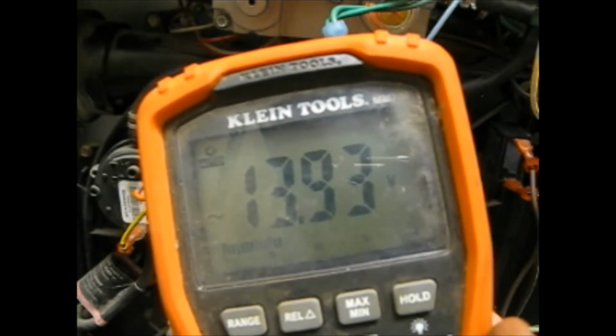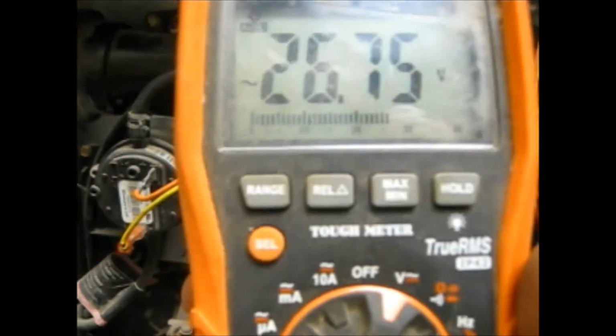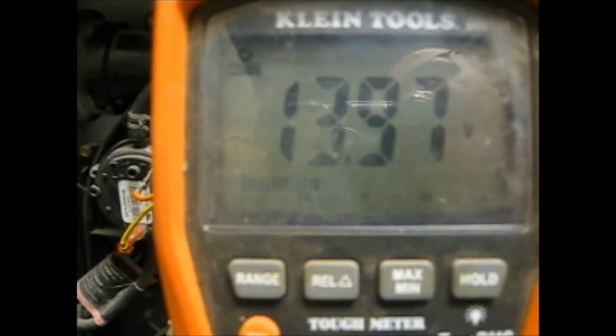Also, at the same time, as I'm holding this voltmeter, I'm also looking into the combustion chamber, looking for that hot surface igniter to go cherry red. It's going cherry red, so there should be a click here shortly. There's the click, and there's our 26 volts, 25 volts. That's exactly what we need. Well, it sensed that there wasn't any flame, so it shut everything down. So that tells us that we have power going to the gas valve.